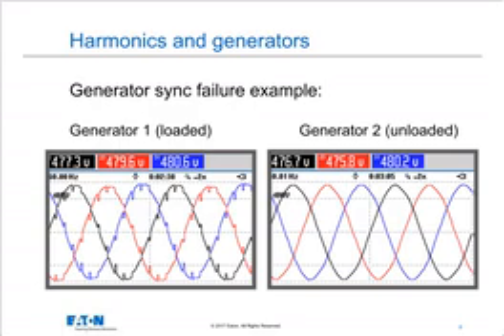So here's an example of an older technology UPS. This happens to be a 12-pulse UPS, and you can see the notches on the left waveform here when that UPS was running on the generator. With the generator running and a significant load on it, you get this amount of voltage distortion, which would correspond to a current distortion if you looked at the current waveform.